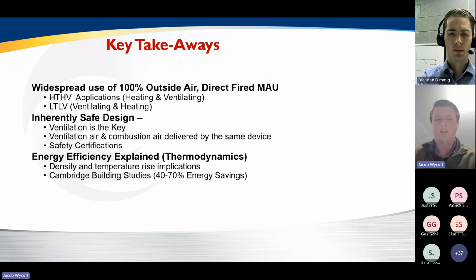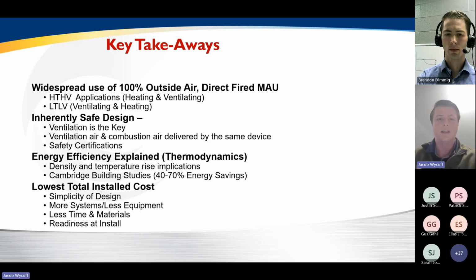We talked in depth about energy efficiency and how the density that the fan sees and the temperature rise can affect the energy efficiency of these units. And we went through a building study that shows 40 to 70% energy savings depending on the technology that you're using at the site. And then finally, we talked about how HTHV can provide the lowest total installed cost due to the simplicity of design, the reduced number of units, the reduced number of systems that you're installing, and the less time and materials needed to install the equipment. As Brandon said, these come almost completely ready to go with all the parts and pieces that you need. And that's the readiness of install.